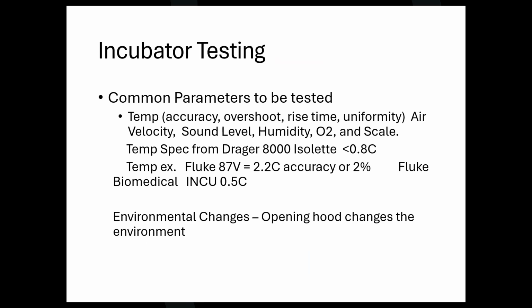All right, let's talk about incubator testing a little bit. Again, I find that a lot of people do not have an idea of what all we need to measure. If I asked you in here, how many of you know what the sound level limit is for an incubator? You're close. The international standard, according to IEC 60601-something, is 60 decibels. Now, the Academy of Pediatrics says 45.